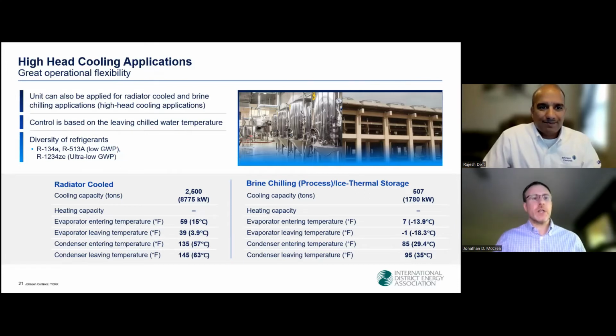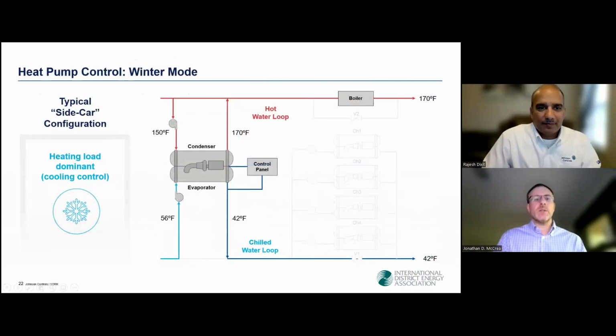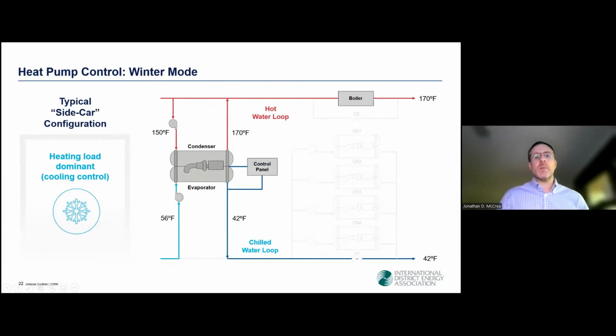All right, thanks, Rajesh. What we'd like to do now is to explain at a high level one of the most common and most economically attractive ways to apply a large water-to-water heat pump. This approach is sometimes called the sidecar configuration, and it's used in a system where there is a need for chilled water cooling and hot water heating year-round. So the heat pump, as you can see, is located where it can be connected to the chilled water and hot water return piping, which is commonly in a central plant where it's close to the chillers and boilers that are already existing.